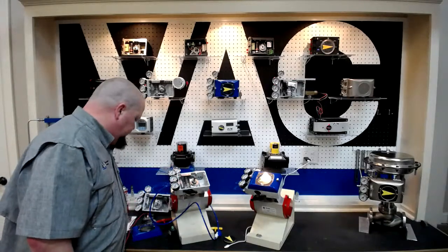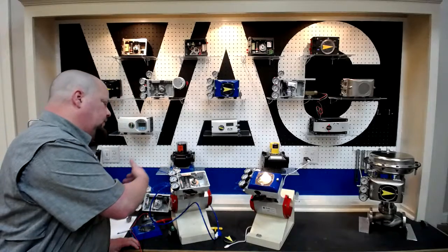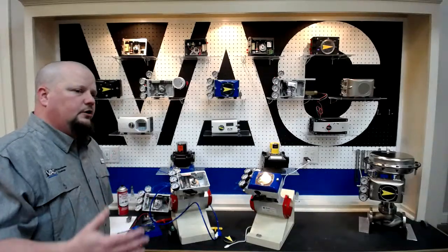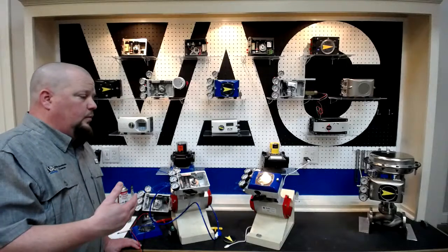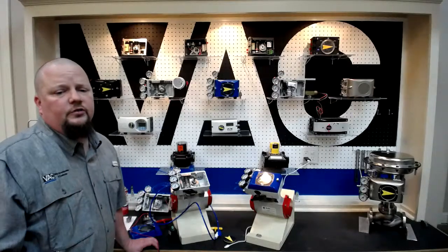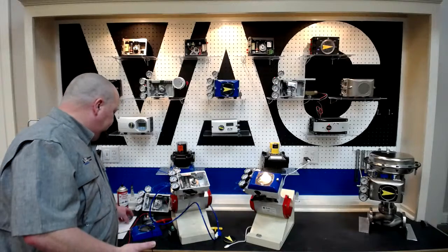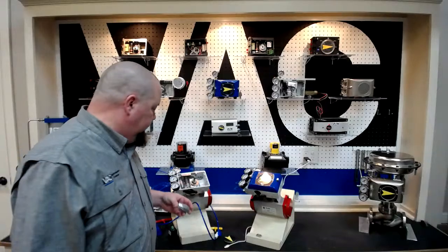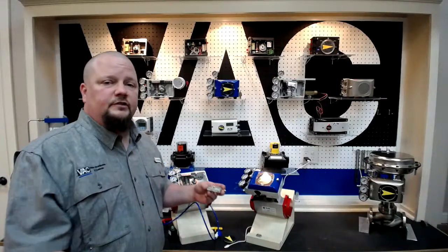Another operation that you don't want to see is, now we've determined that everything works, but we have to see a large increase in signal to get the positioner to move. Or when we do see the positioner move, it overshoots and comes back and it's hunting back and forth. We call this oscillation, and what that's generally due to is contaminated air. Your pilot valve gets a bunch of trash in it. What we're going to try to get you to do is say, hey, do me a favor, cut the air off. Let's pull the pilot valve and check it.